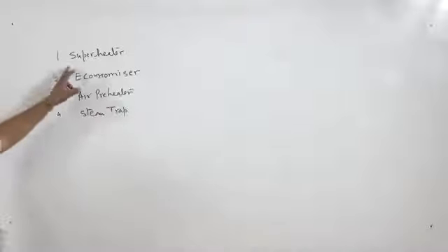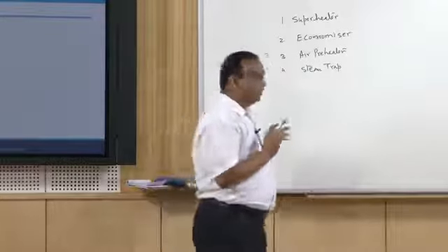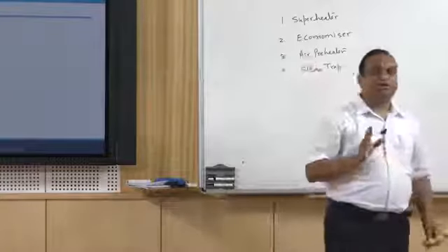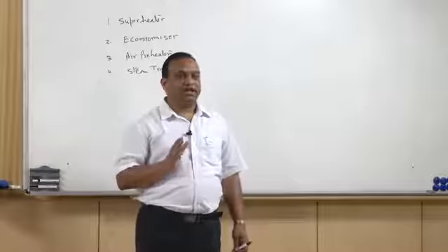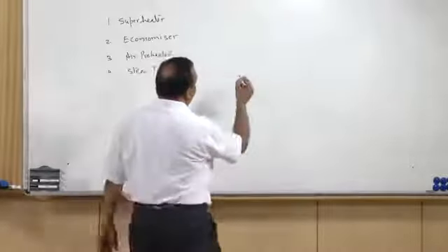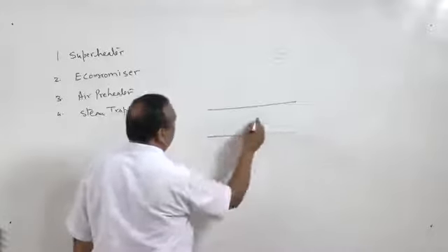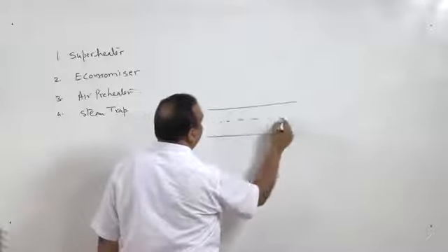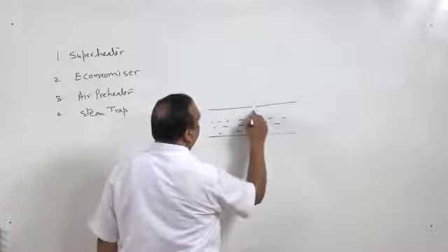Now, superheater means steam superheater, because we need superheated steam in order to have higher efficiency. When you superheat the working fluid, the average temperature of heat addition increases, and this imparts higher efficiency to the cycle. So, for the superheater, as you must have seen in the previous lectures also, in the shell there is a mixture of liquid and vapor.